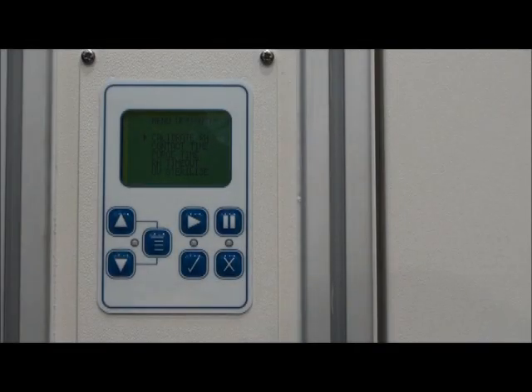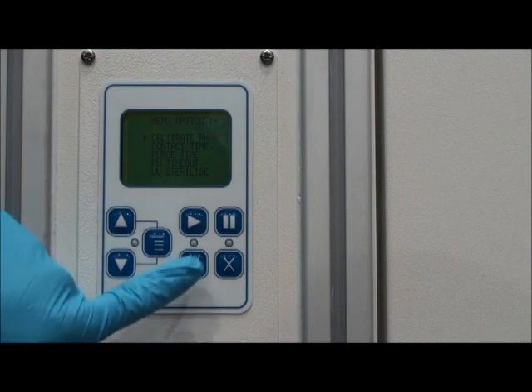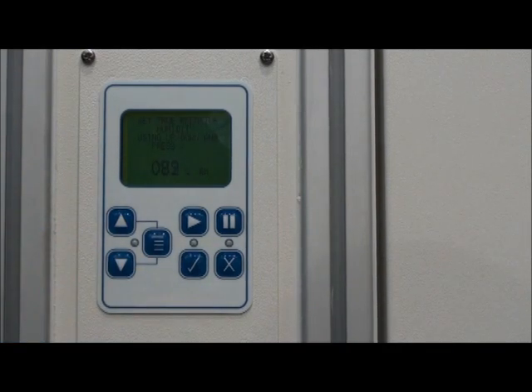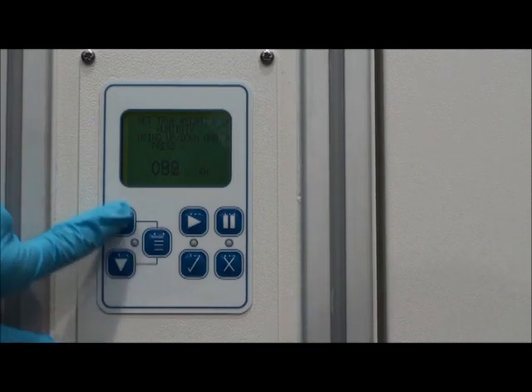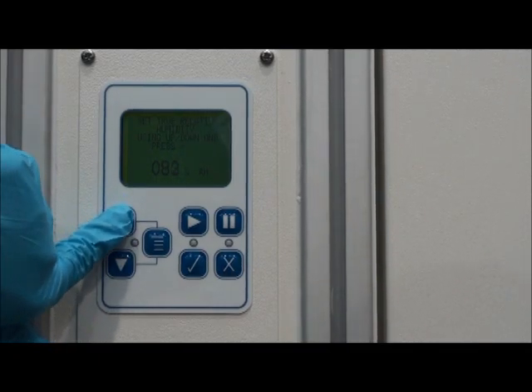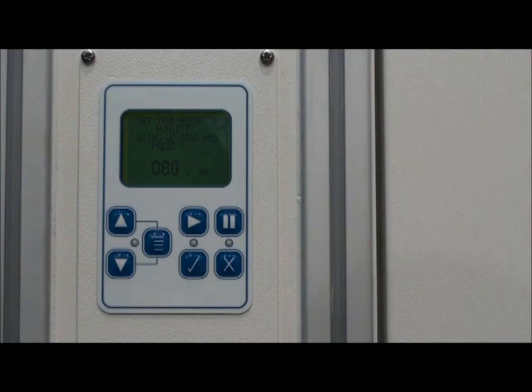First we're going to access the humidity calibration. To access this, you press the tick key when the arrow is opposite, and that brings you into the submenu, which is displaying the humidity. Pressing the up and down keys takes it upwards and downwards, and pressing the tick key accepts the setting. We'll discuss calibration in more depth towards the end of this video.